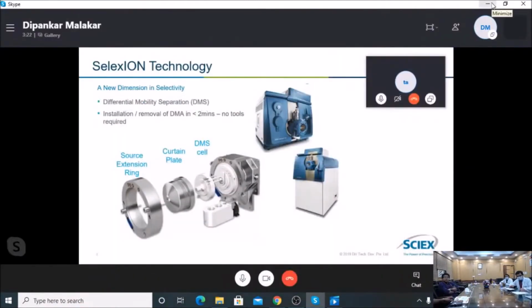If somebody wants to use the Selexion on the 6500, which is actually a Q-trap instrument, we are able to do MRM and also the enhanced product ion scan together using the trap functionality. Apart from that, there are many other scan functions like neutral loss or precursor ion scan, which is typical for triple quadrupole mass spectrometers.